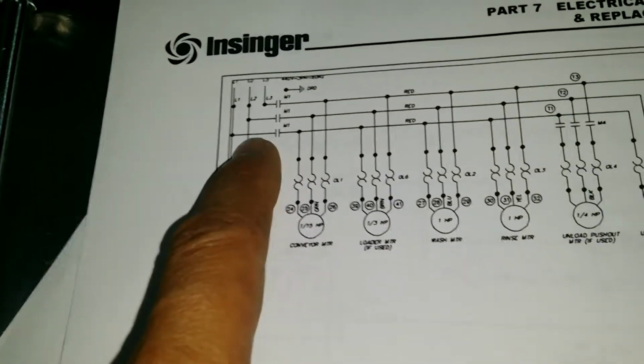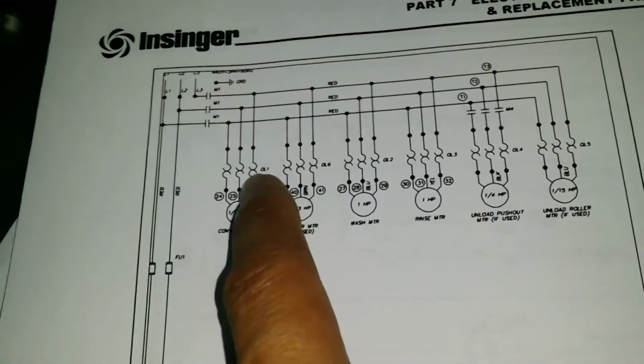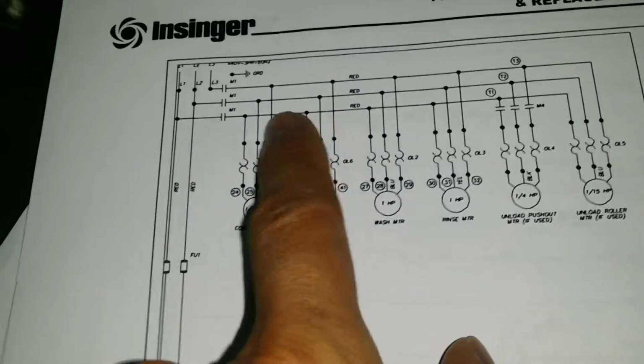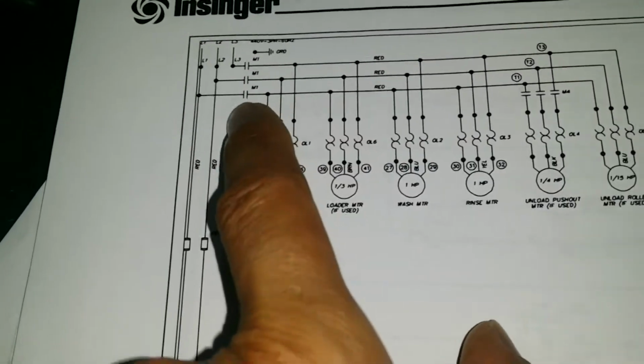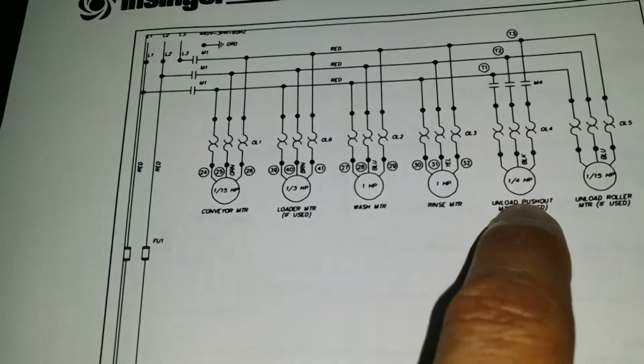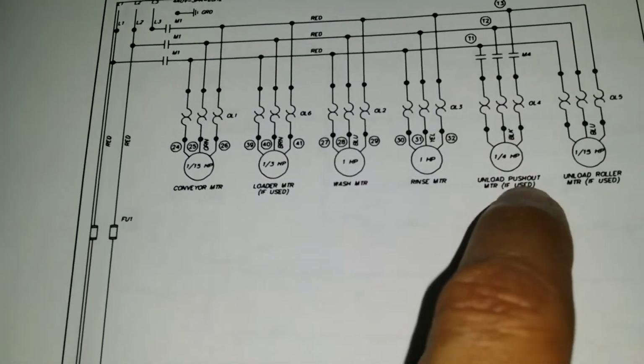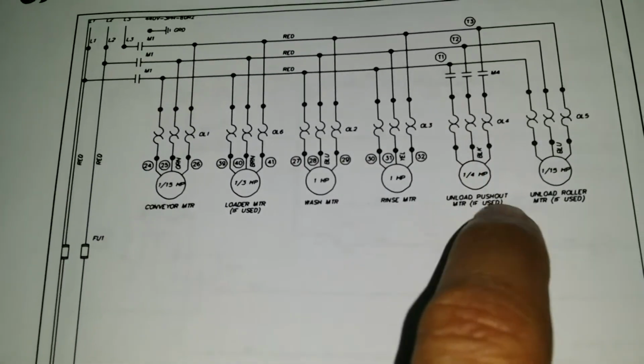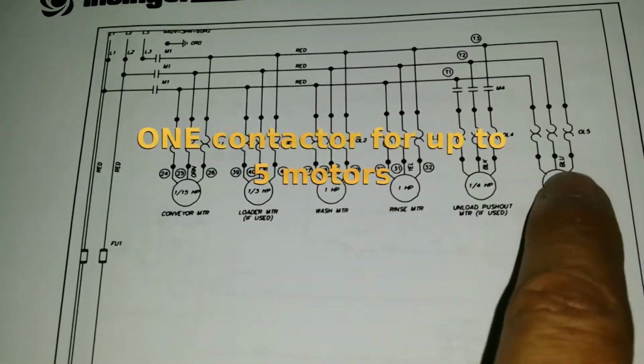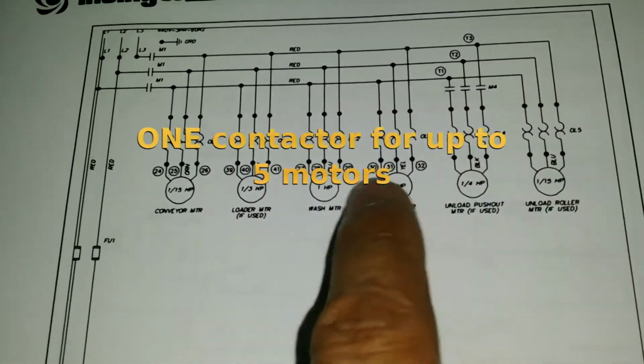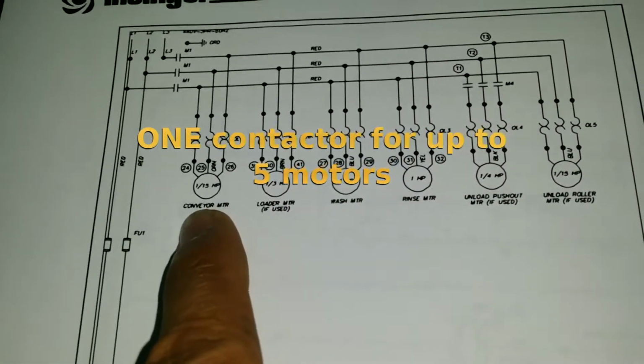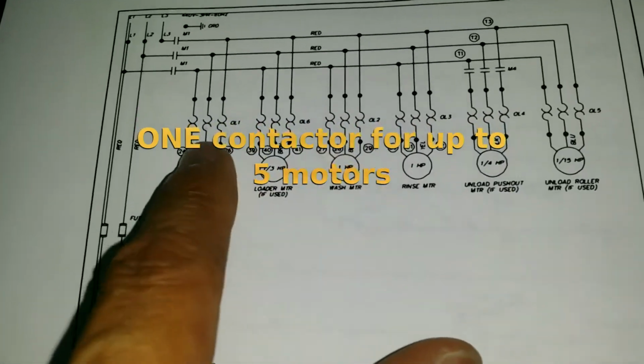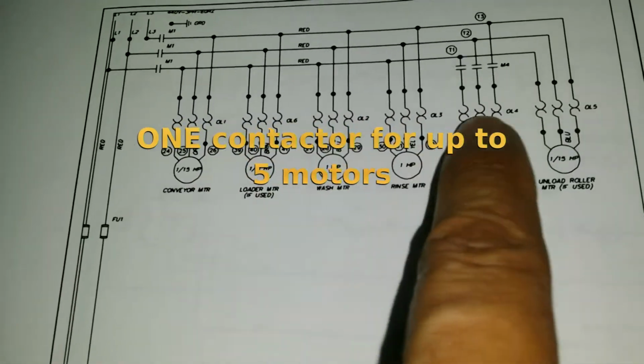If you look at the schematic, we have a lot of motors, but pay attention to this. There is only one contactor. Well, sometimes there is another contactor if they use the unloaded push-out motor. But if that's not the case, one contactor provides power to 1, 2, 3, 4, 5, up to 6, up to 5 motors. Notice that each one of them has its own overload.